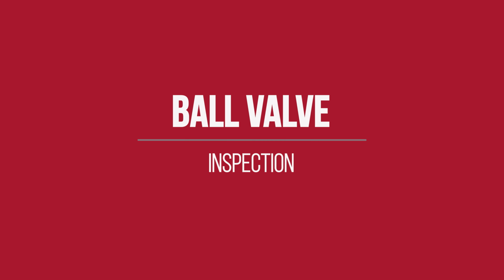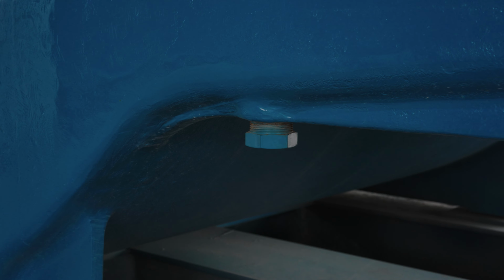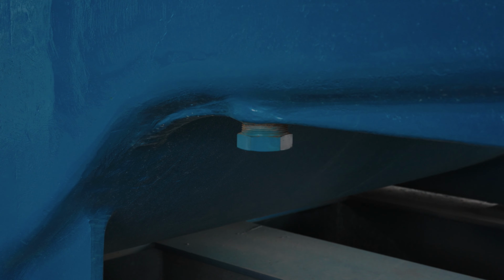Under the front of the pump frame, you'll have a 2-inch ball valve to drain the water off the oil. When you gently crack open the ball valve, you'll see water come out. Once you see oil only, close the valve. This is a daily duty.